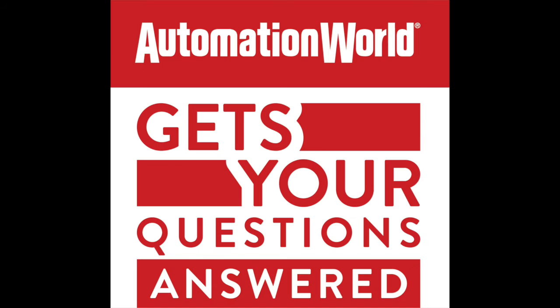Yeah, that's a great question, and the important thing of understanding what to use where is also the limitations of each of these devices. So an air conditioner, for example, is a closed loop system, so you're never bringing anything from the ambient air or whatever outside into the enclosure. But they've got a maximum operating temperature, after which point they don't become efficient any longer. And that's in the neighborhood of maybe 131 to 140 degrees Fahrenheit, depending on the manufacturer and the technology they use. So even though you want to use that in warm or hot environments, there's a limitation to that. And again, it's right around that 130-ish standpoint.